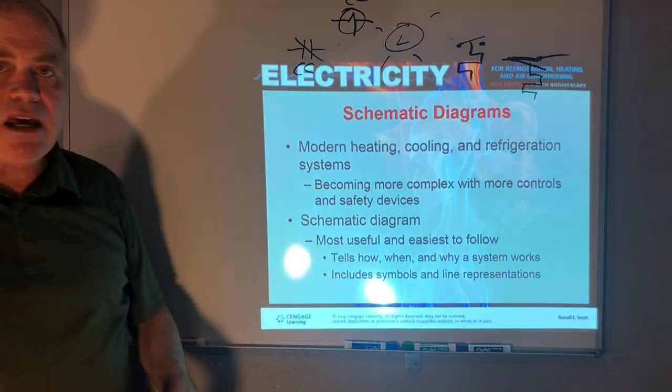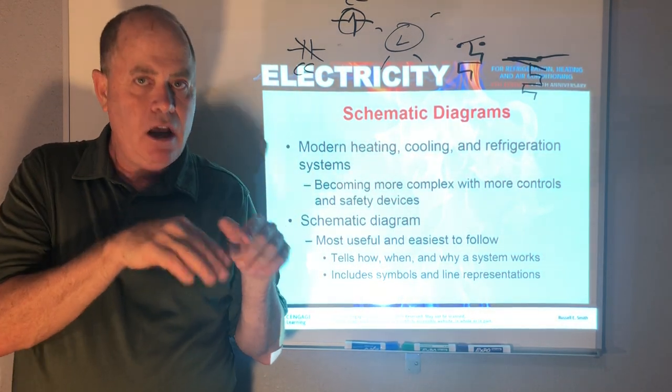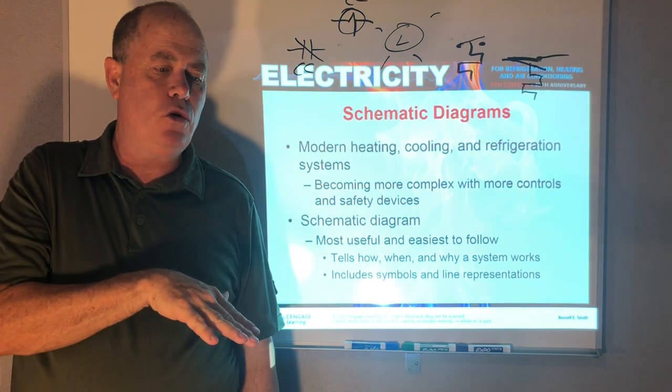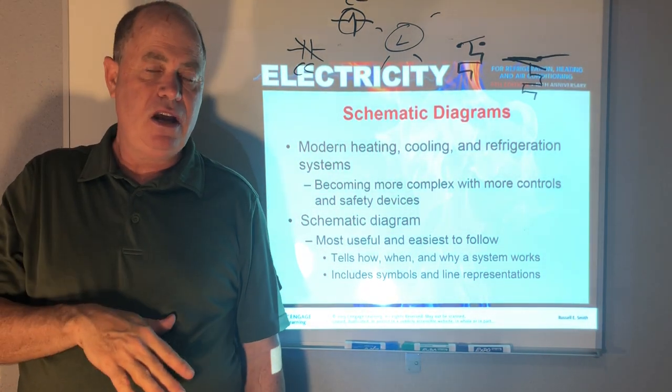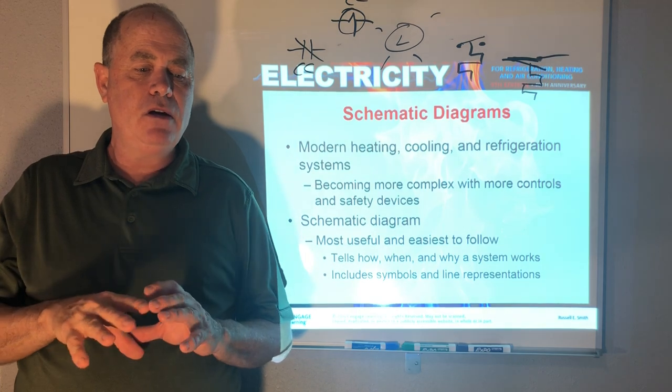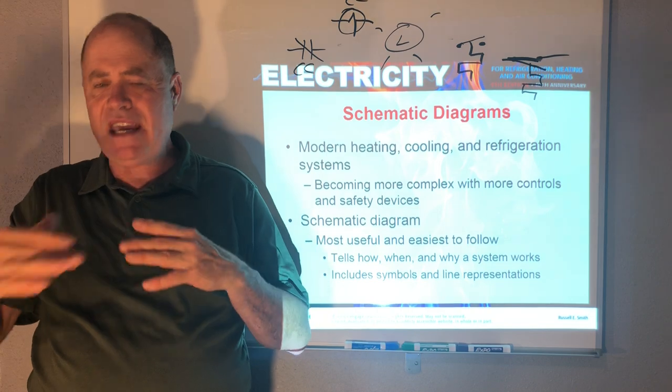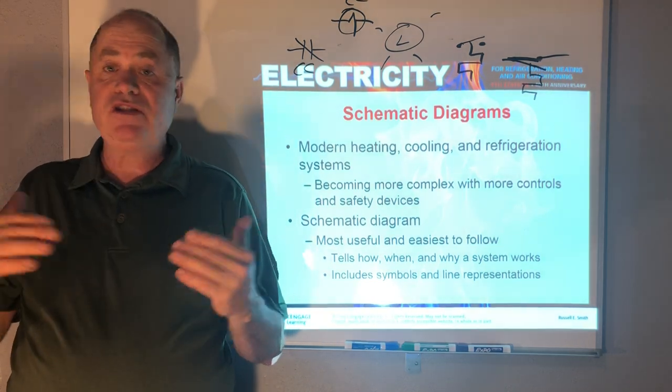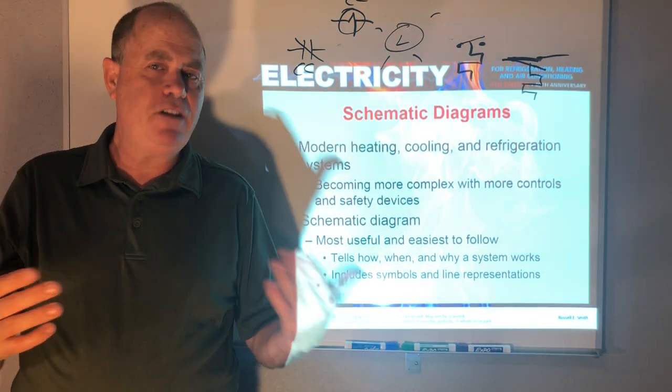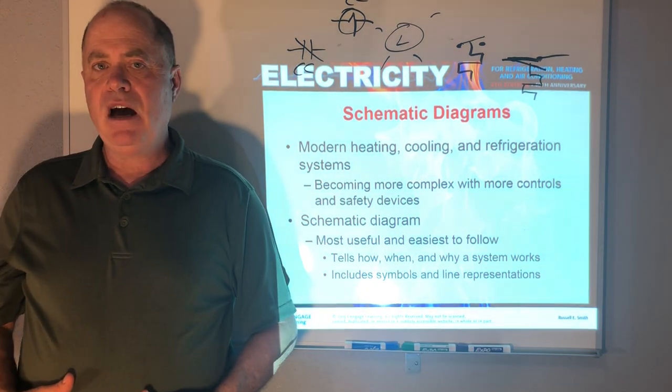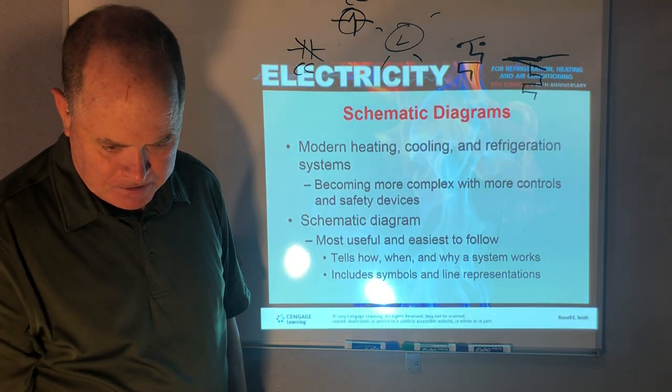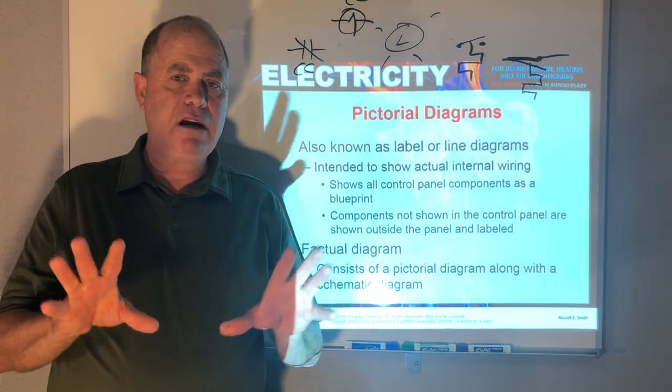A schematic diagram is also known as a ladder diagram. And it really helps you with sequence of operation. It doesn't show you where each wire terminates, but it shows you which control controls what loads. And it's drawn for the purpose that it's easy to look at and easy to read so that you can understand how the system works, what controls what, and it helps you to figure out what's wrong with the system and to do proper wiring.